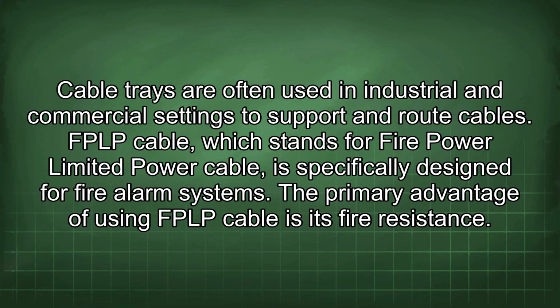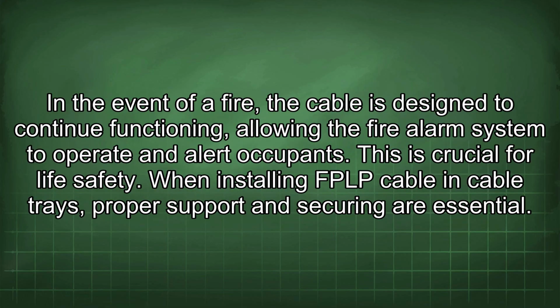The primary advantage of using FPLP cable is its fire resistance. In the event of a fire, the cable is designed to continue functioning, allowing the fire alarm system to operate and alert occupants. This is crucial for life safety.